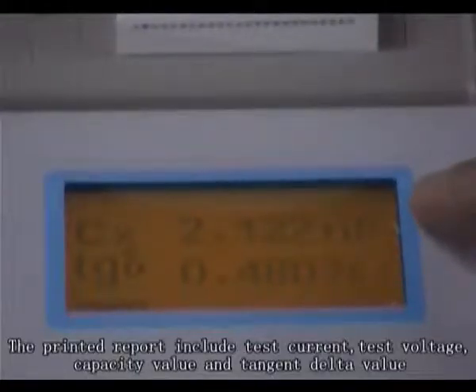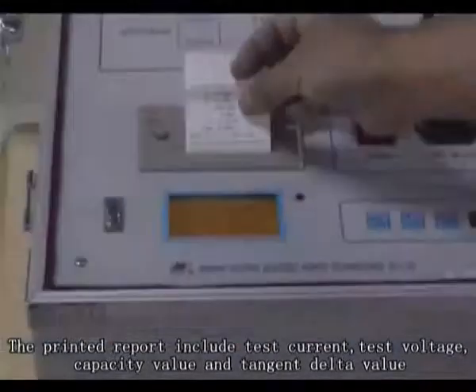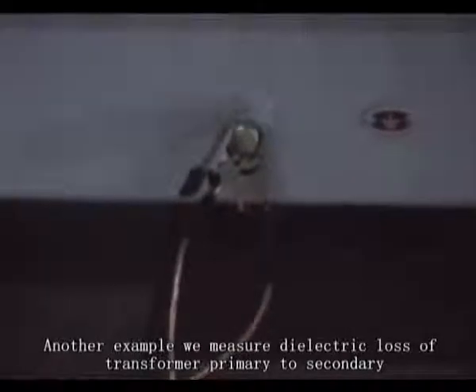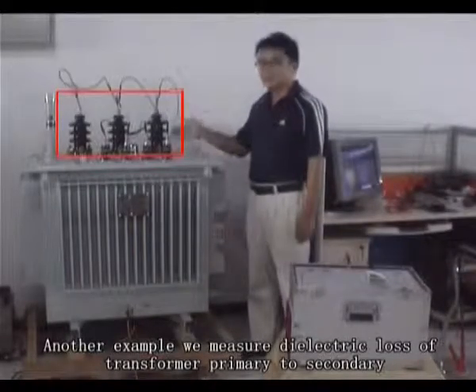You can print the test results. The printed report includes test current, test voltage, capacitive value, and tangent delta value. Another example, we measure dielectric loss of the transformer primary to secondary.